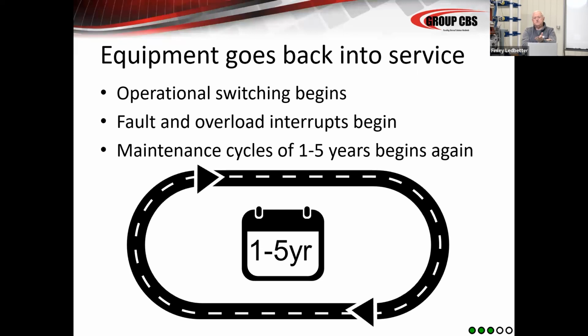So in these, you continue to catch now the degradation. So now you start to catch things are degrading. You'll find through acoustic or PD, you will find some insulation breakdowns. You will find some operation issues. For instance, these vacuum breakers have wear limits. So they have to be maintained at a certain wear limit, and each vacuum interrupter has a different wear limit. Also, they'll operate pretty well up to about 1,000 operations. Beyond 1,000 operations, you start to get wear out mechanically. Now, a lot of people say 1,000 operations. My breakers see 200 or 300 operations a year, or 20 operations a year, or 1 operation a year. There are a lot of breakers out there that are in repetitive application duty that see thousands of operations a year. And sometimes at about 3,000, the mechanisms are pretty much in a condition to where they have to have major maintenance. We'll get to that in the next cycle here.